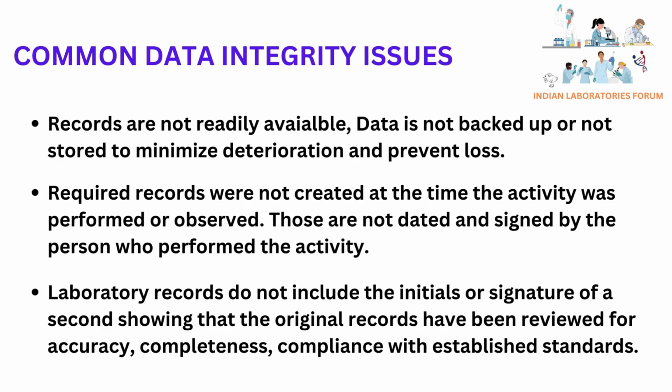Records are not readily available, data is not backed up and not stored to minimize deterioration and prevent loss of data. Required records were not created at the time the activity was performed or observed. Those are not dated and signed by the person who performed the activity. Laboratory records do not include the initials or signature of a second person showing that the original records have been reviewed for accuracy, completeness, and compliance with established standards.